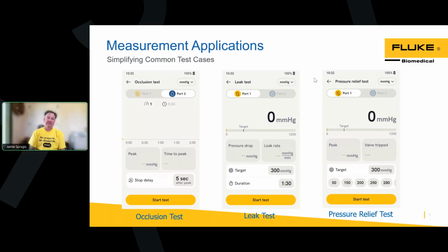It will calculate your pressure drop and your leak rate. And then last, you got your pressure relief test. Probably my favorite test of all. If your non-invasive monitor requires a pressure relief test, here again, default port 1. You select your target, and the target is the target that it's going to pump up to.